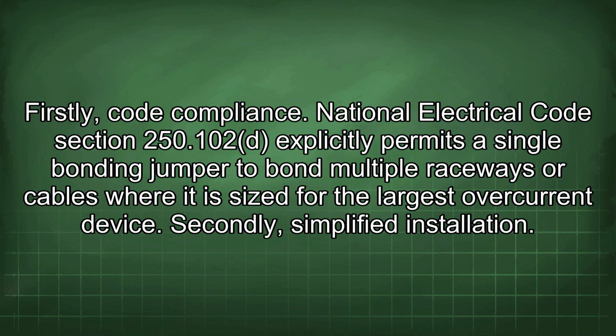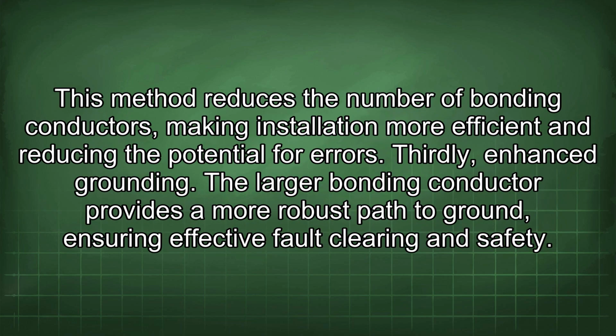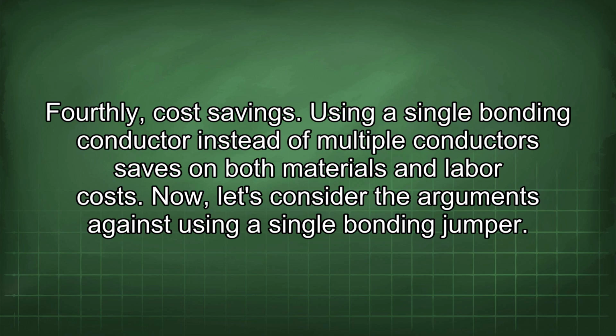Secondly, simplified installation. This method reduces the number of bonding conductors, making installation more efficient and reducing the potential for errors. Thirdly, enhanced grounding. The larger bonding conductor provides a more robust path to ground, ensuring effective fault clearing and safety. Fourthly, cost savings. Using a single bonding conductor instead of multiple conductors saves on both materials and labor costs.